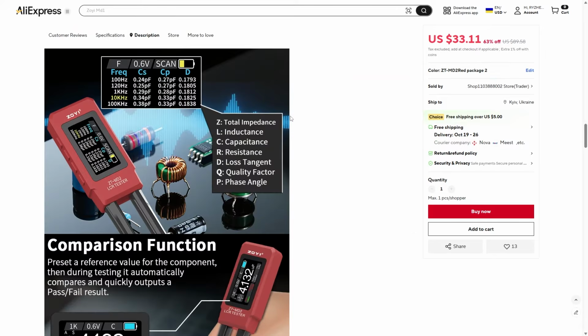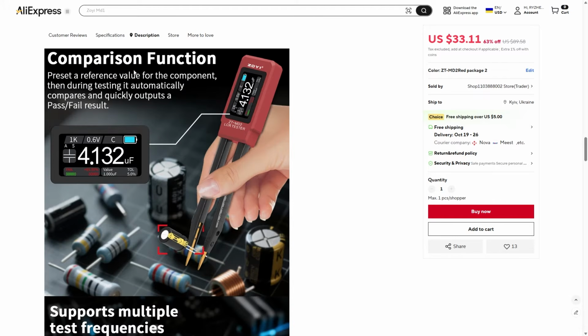Now let's count the advantages. The first advantage is that it has a scanning mode. A component can be scanned quite quickly at 5 frequencies with a parallel measurement circuit, a series measurement circuit, and an additional parameter is measured. For capacitance, this is the dissipation factor. The second advantage. It has a comparison function. Regarding the comparison function, I couldn't find how to enable it in the manual. Most likely, this function requires additional software.